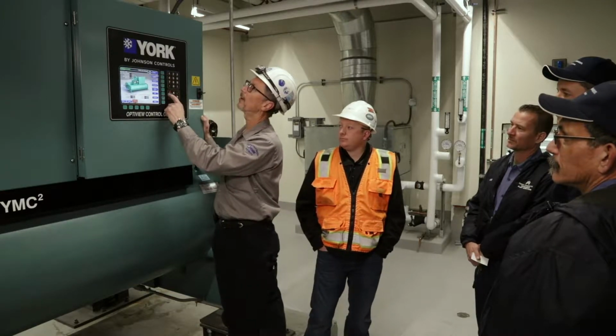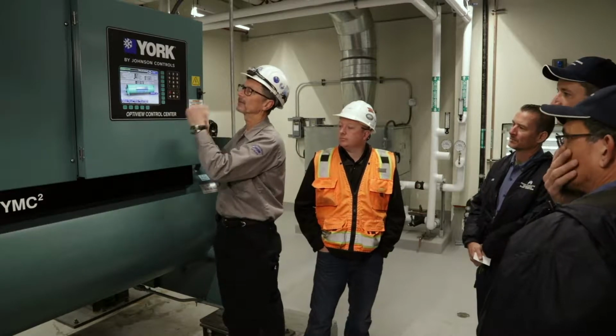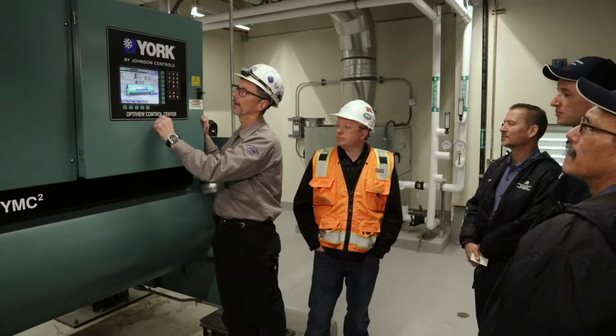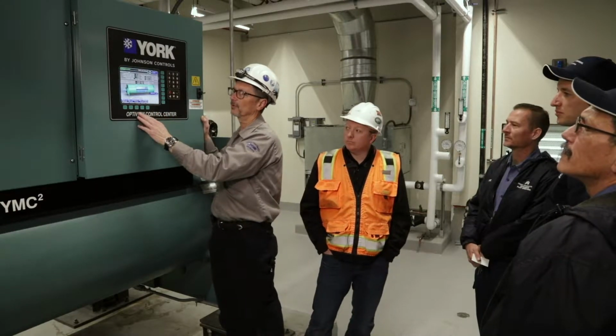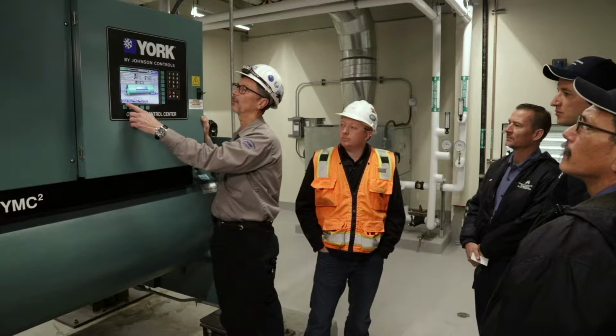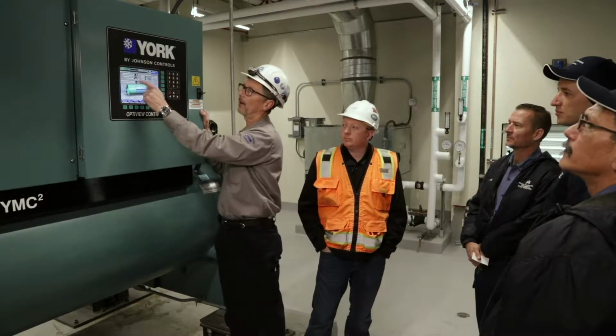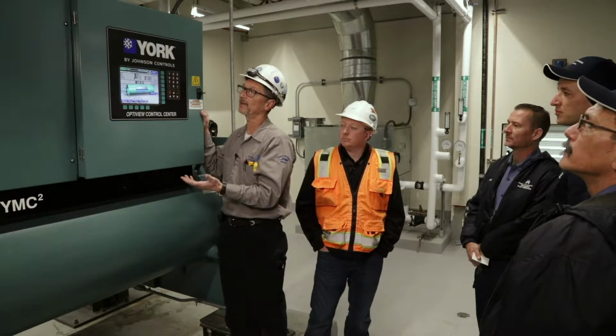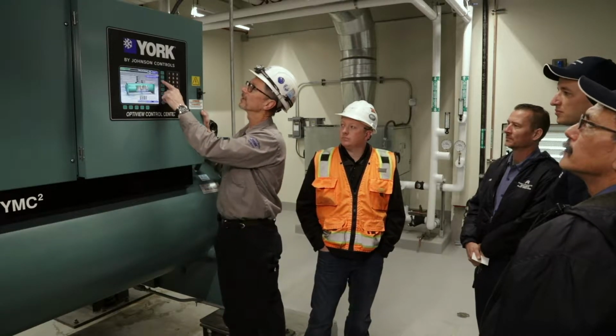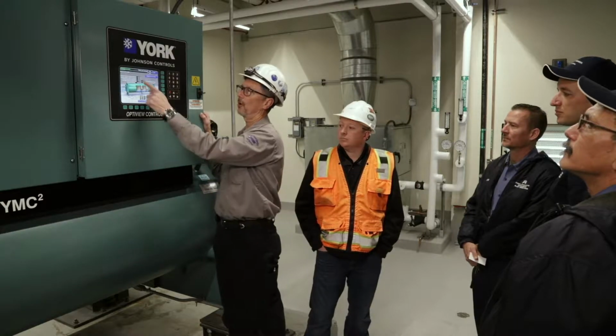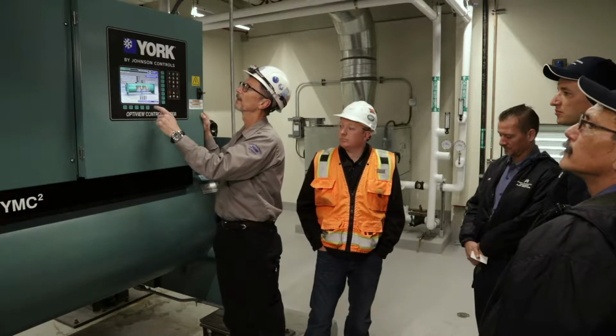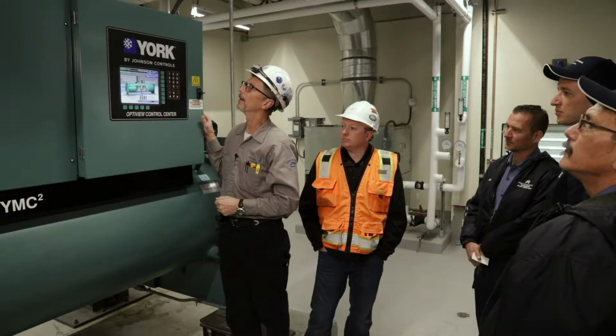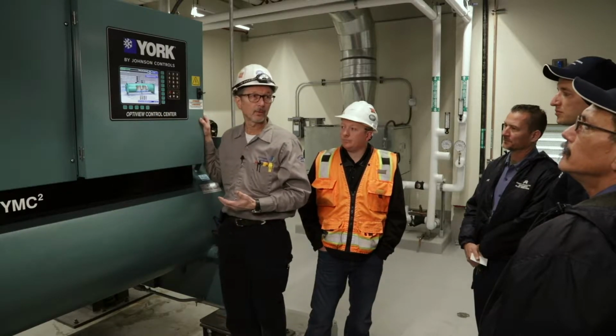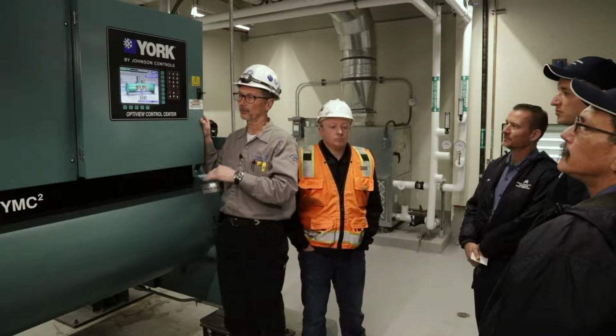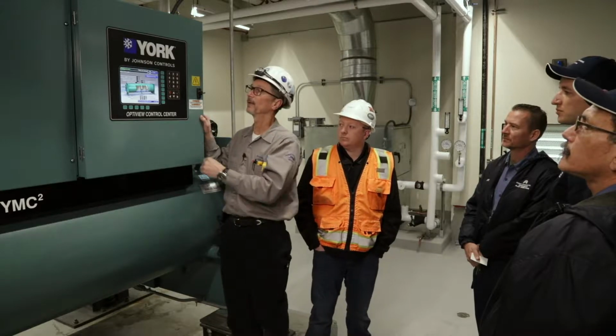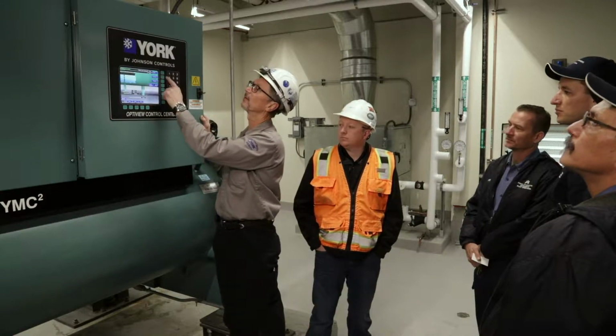To look at a specific component, you can go to the evaporator and you can see the temperature settings and the setting for when the chiller shuts off and when the chiller restarts, and the set point that it's trying to control to. And then all the specifics of what's happening at that moment inside the evaporator. On the condenser screen, basically the same thing. It shows you all the condenser settings, and there is a setting, a refrigerant level control, that maintains a certain liquid level inside the condenser for efficiency, and that setting is on this screen as well.